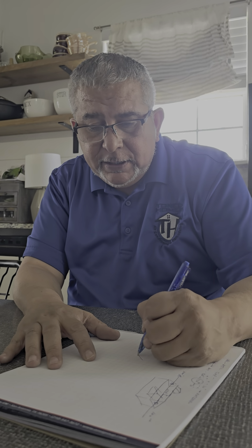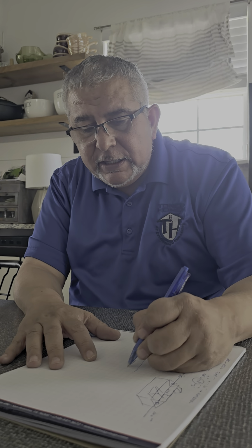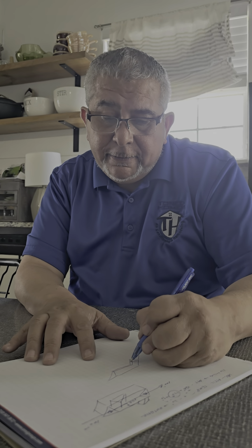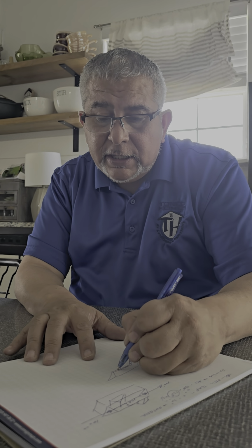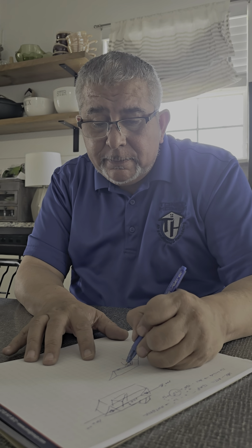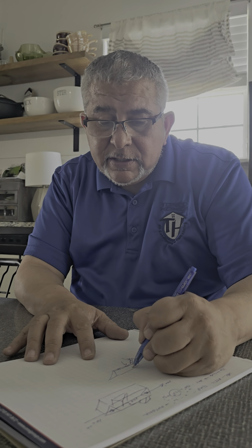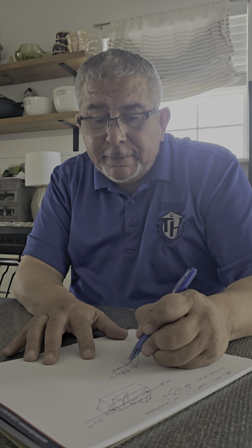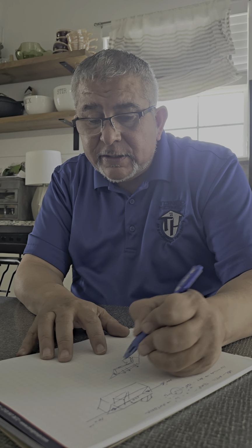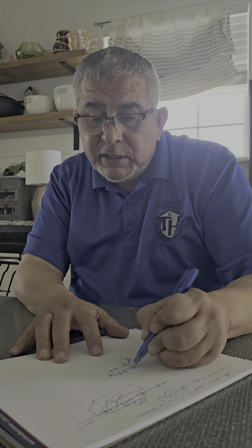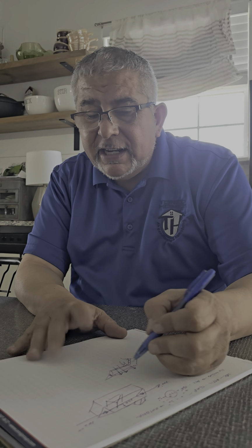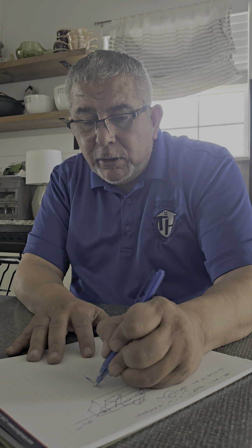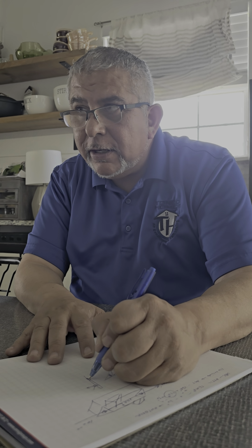Well, on a house that's cut up, that has varying angles, what you do a lot of times now in modern day homes is they have holes cut in the overhangs, and the air comes in from the bottom, and then we have, let's say, a ridge vent, and the air is supposed to go out of the top. And that's perfect. In that case though, we don't want any gable vents because we want the air to be forced this way. It's kind of like a straw. If you're drinking from a straw and you want it to go this way, you can't have a hole right here, because then you're not going to draw anything from here.